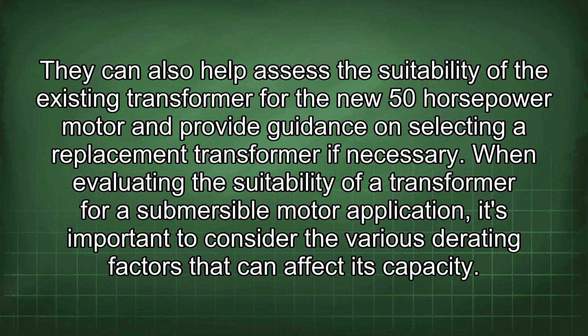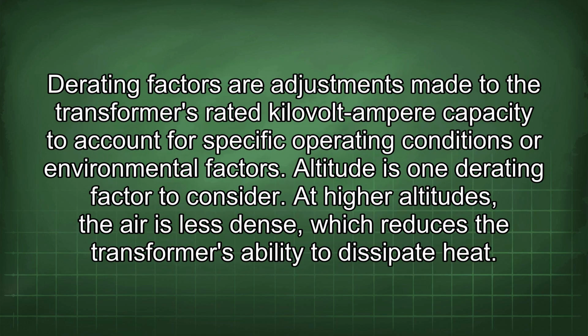When evaluating the suitability of a transformer for a submersible motor application, it's important to consider the various derating factors that could affect its capacity. Starting factors are adjustments made to the transformer's rated kilovolt-ampere capacity to account for specific operating conditions or environmental factors. Altitude is one starting factor to consider. At higher altitudes, the air is less dense, which reduces the transformer's ability to dissipate heat.